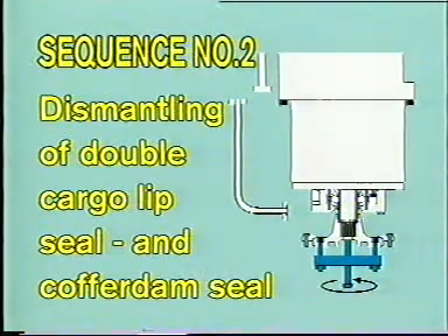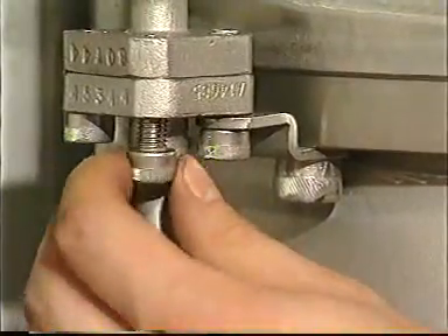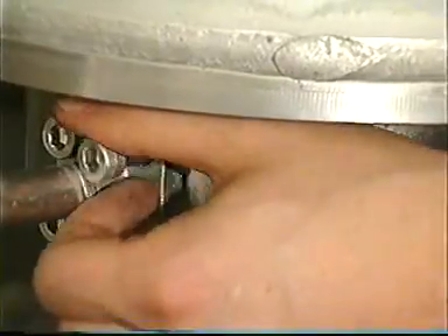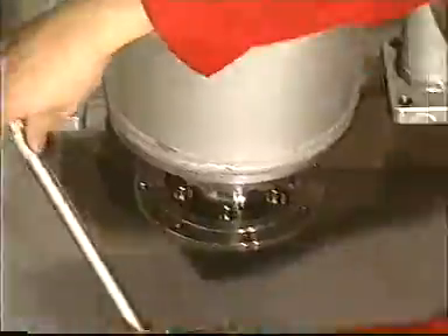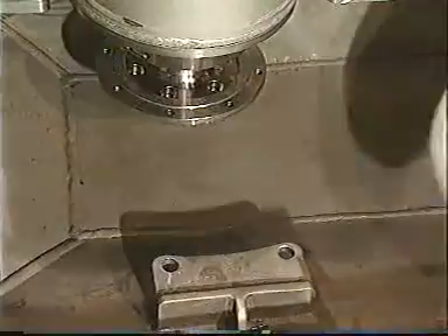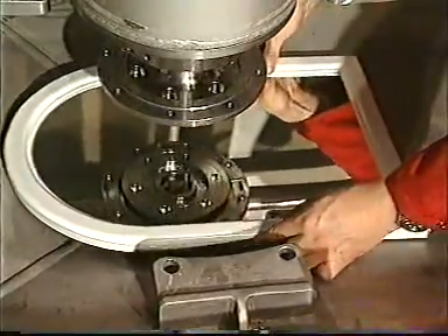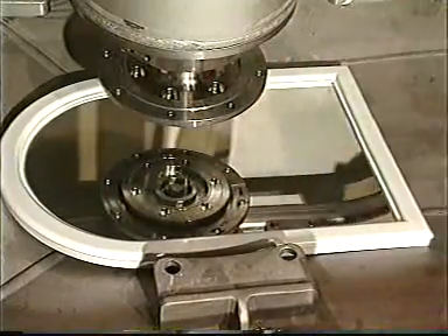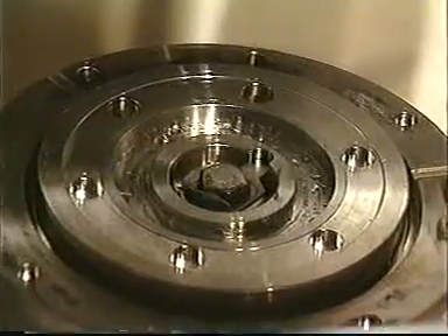Sequence number 2. Dismantling of double cargo lip seal and cofferdam seal. First, dismantle lower part of cofferdam check pipe. Then dismantle the impeller hub from the pump's shaft.